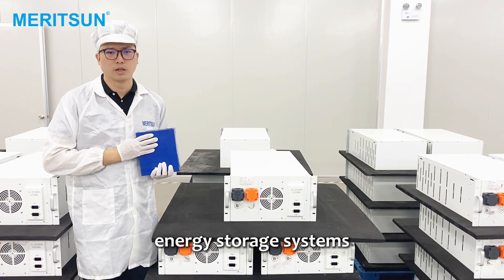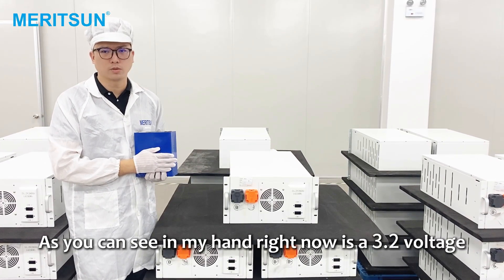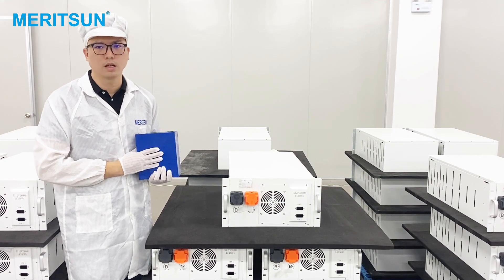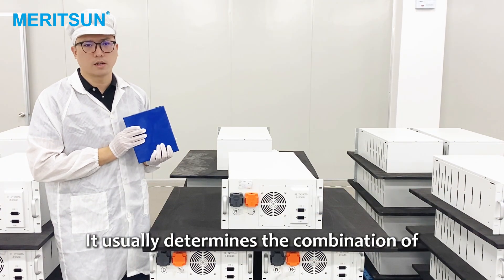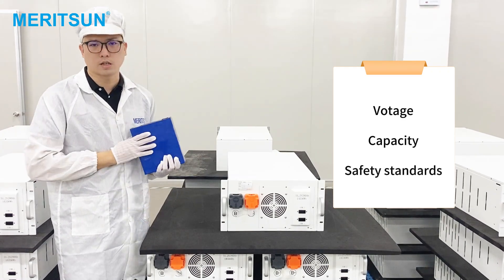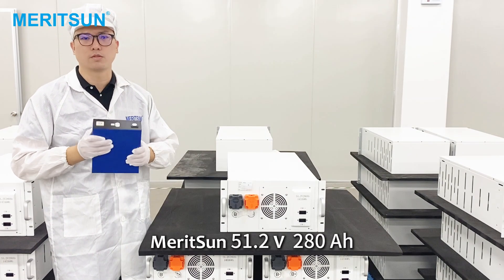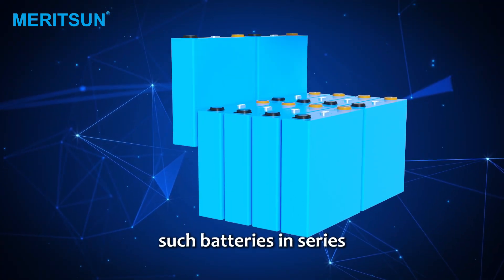To ensure that we can produce high-quality energy storage systems, Meritsun uses new grade-A LiFePO4 cells. As you can see, in my hand right now is a 3.2-voltage, 280Ah cell. The number of cells required to form a battery pack is closely related to the specific application scenario and design specifications. It usually determines the combination of cells based on the required voltage, capacity, and safety standards. The connection between the cells uses laser welding technology, which ensures the stability and conductivity of the connection. Meritsun's 51.2-voltage 280Ah battery pack is assembled by 16 such batteries in series.